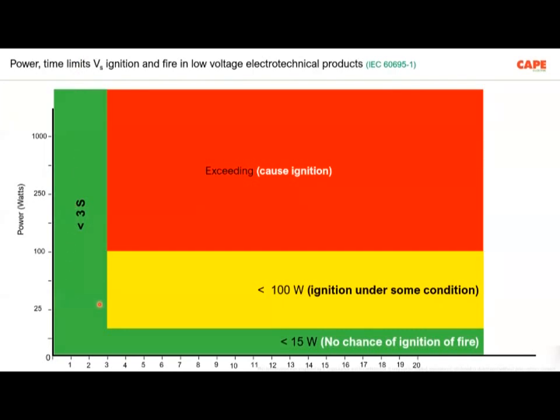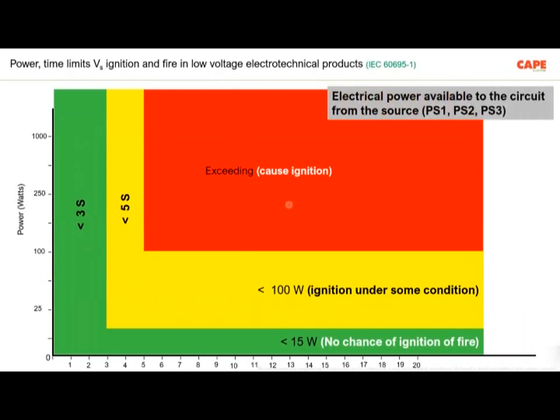If we are able to limit the fault to less than 15 watts within 3 seconds, then the chance of ignition of fire is less. In simple words, if your MCB trips within 3 seconds, the fire chance is less. Similarly, if the protective device is operating within 5 seconds, ignition is possible only under some conditions. These are some of the concepts considered for designing an electrical apparatus plus designing an electrical circuit with respect to safety.